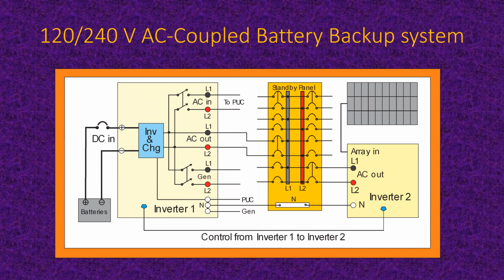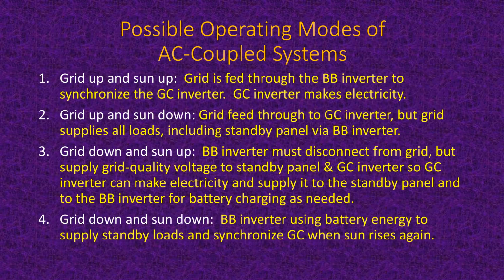And that's what makes the AC coupled systems kind of interesting, because of the way the two inverters have to talk to each other. Now, this inverter in this AC coupled system, if we're looking at, say, a Powerwall system, the inverter will be right inside the battery case, inside the Powerwall. And that Powerwall is then designed to have communication to talk to inverter number 2. Okay, so again, getting the general idea of how this thing works helps a whole lot in understanding what's out there today. So let's move on. And this is what we just talked about, the 4 different operating modes. So you'll get this in your notes if you send off for the slides, and you'll see exactly, again, a reminder of what kind of control has to take place here in order for the system to function properly.